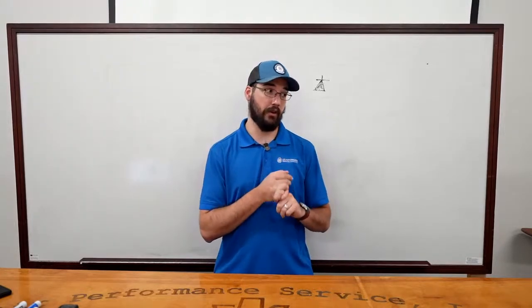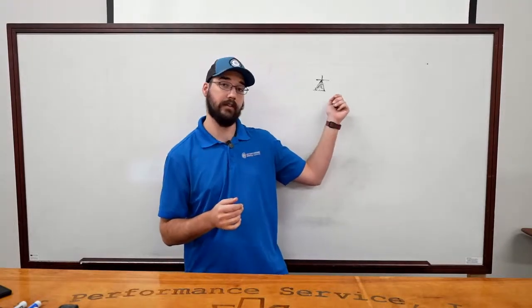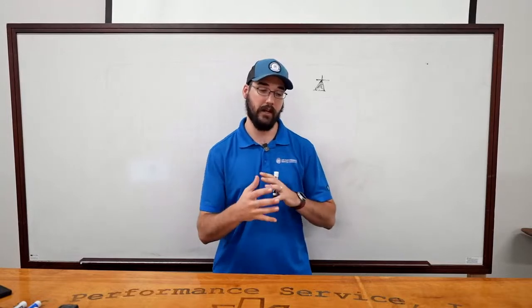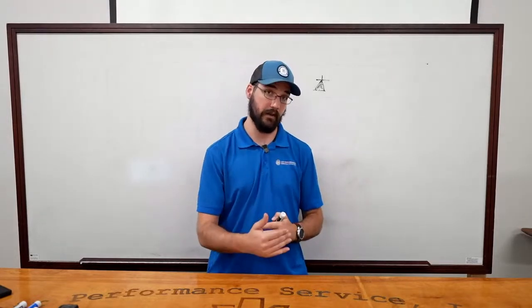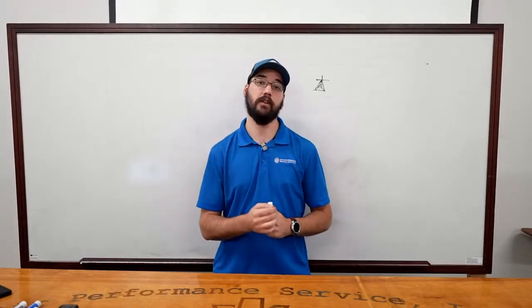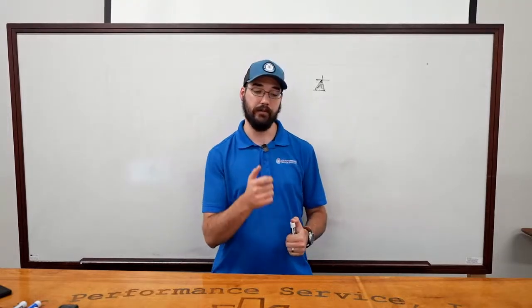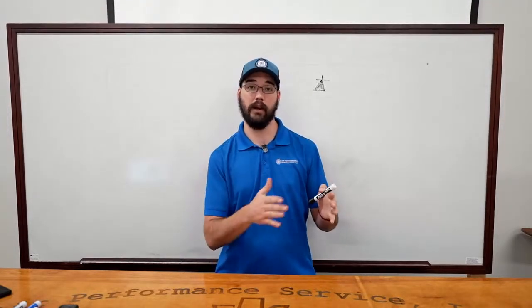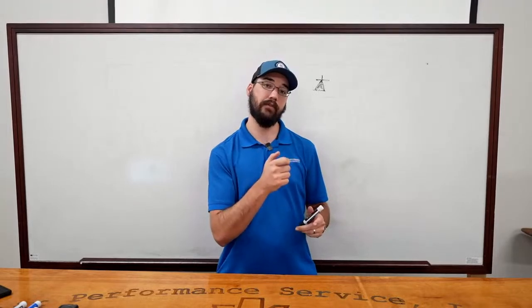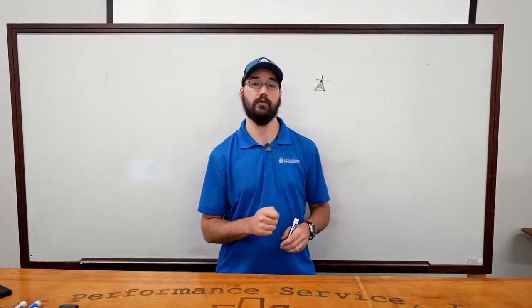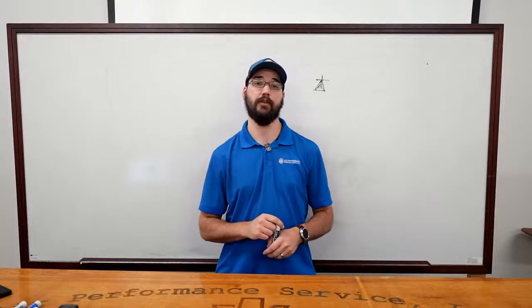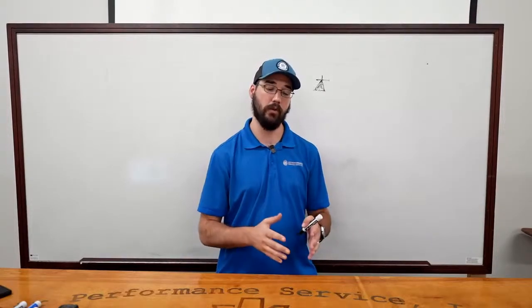To troubleshoot inverters, you're really going to need to understand diode tests and continuity and being able to read resistance properly through your meter. And I don't recommend doing these things in an auto range. Even if you have a meter that is auto ranging, you should have the function of being able to manually set those ranges. You're going to want to do that when you're doing these types of troubleshoots.